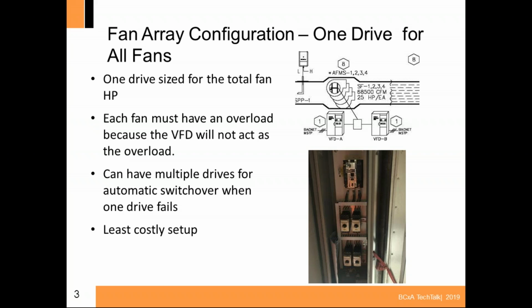A lot of times, like when I do a lab system, let's say I've got 3 big Greenheck fans on the roof, it's almost like a fan array because it has different fans on one big plenum. We'll run one, and before the other fan starts, we'll draw a DP across the inlet damper into the exhaust fan and get it almost as negative as the current plenum, and then we'll start cracking that fan open. That's a direct drive application also, so I like doing it that way too. Anyway, I didn't mean to go off on a tangent.